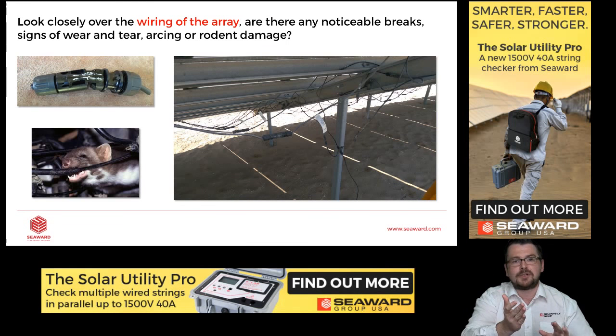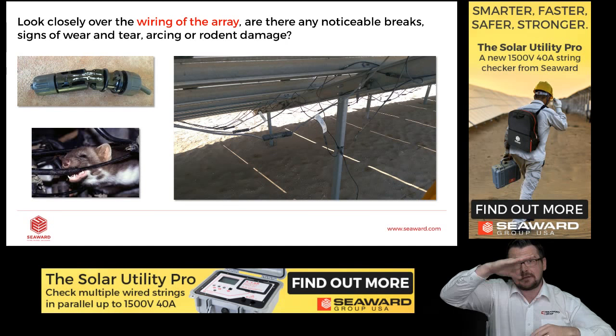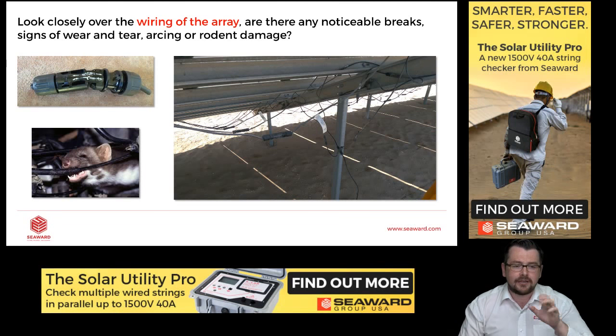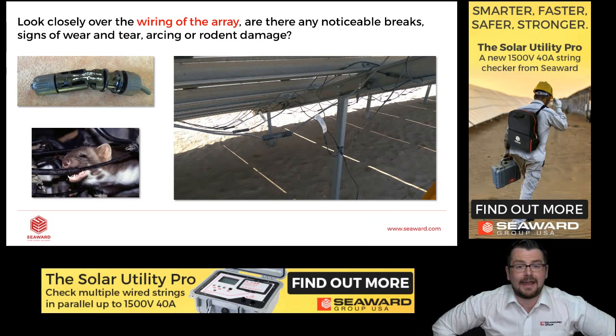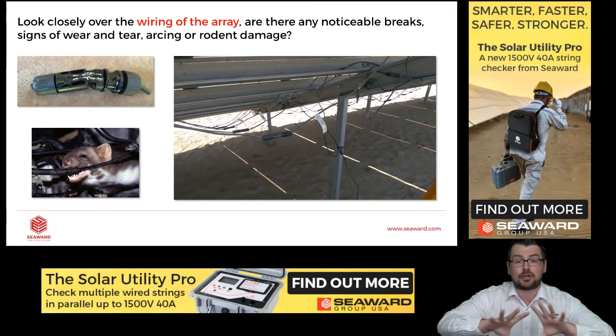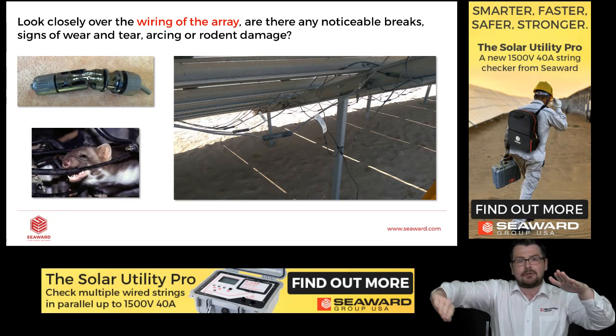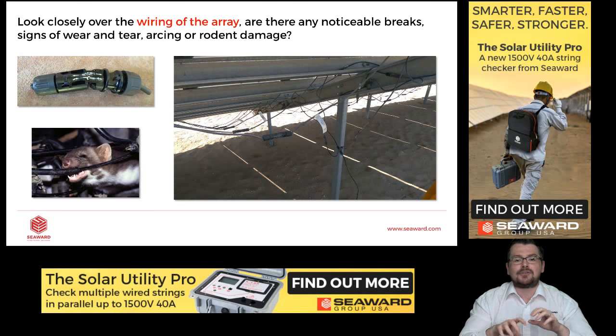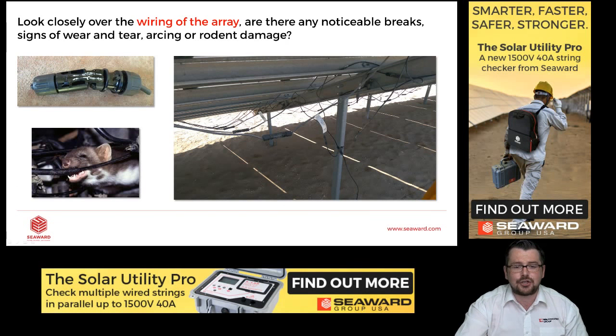So while you're doing your visual inspection, if you see any cables hanging down, just lift them up, maybe cable tie them and secure them properly. They shouldn't be looking like this. You'll notice the image of the rodent in the bottom left-hand corner. This can be particularly a problem when we have solar farms in the middle of a field, in a grassy field. If the cables are lying down inside the grass, rodents and small mammals, they do like to chew the cables. So do watch out for this. And also with these kind of arc faults and smoldering, you might have a sensation in your nose. You might be able to smell the arcing also.